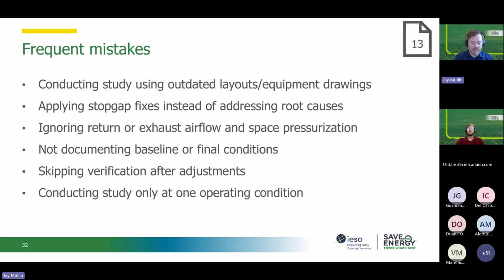And lastly, a common error is conducting the balance only at one set of operating conditions. So I mentioned before the importance of testing airflow under multiple load scenarios, shift changes, different seasons when different equipment's running, to make sure you do have that dynamic stability. So as the conditions in your facility change, it's able to adapt with those to maintain the comfort and proper balance of pressure, regardless of operating condition.